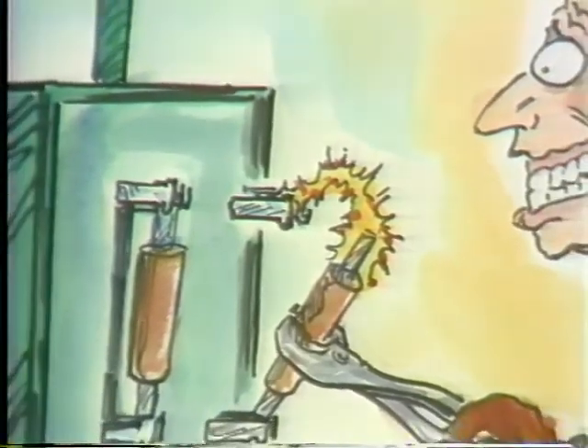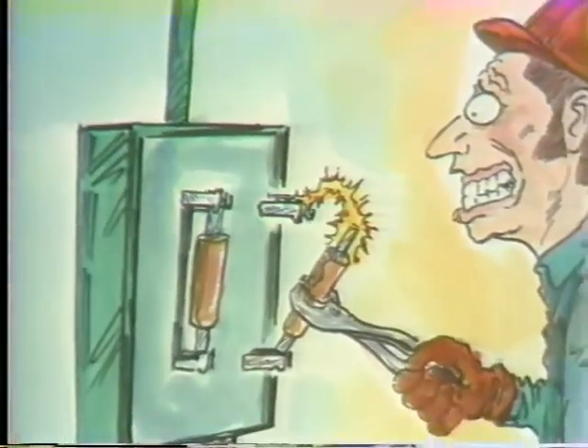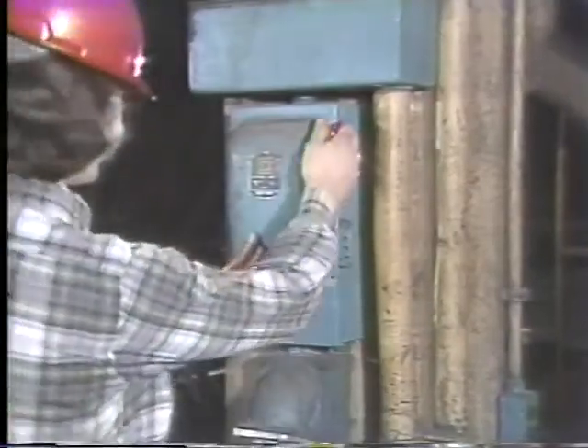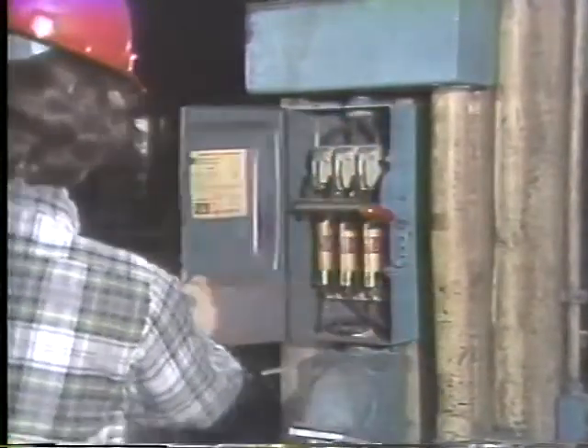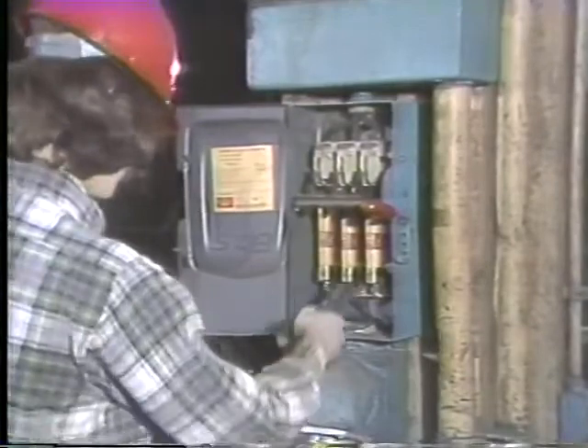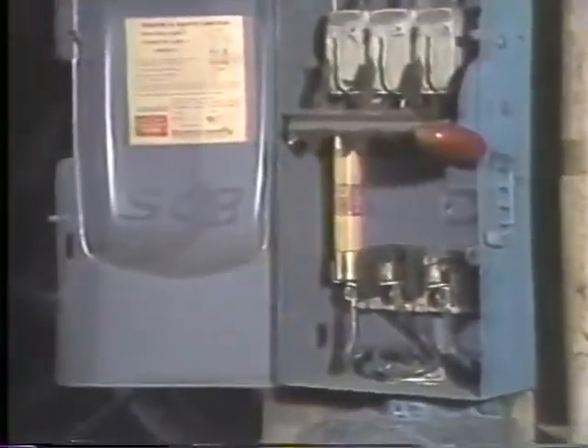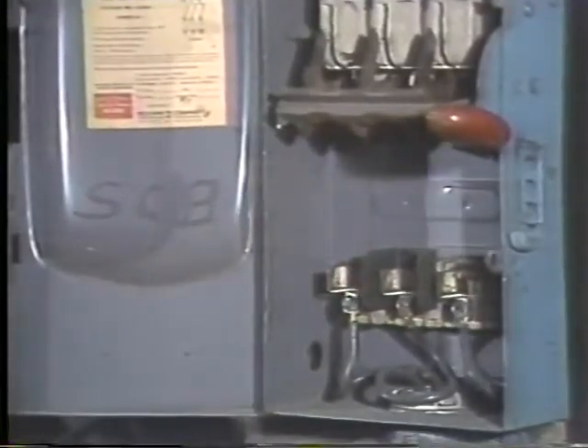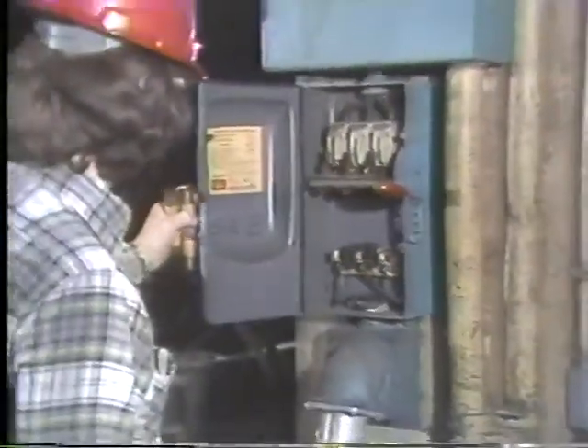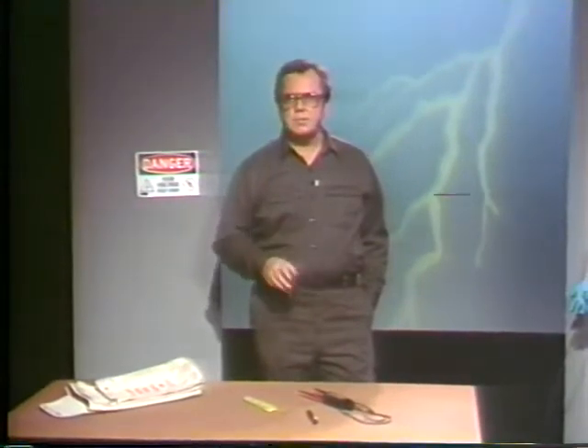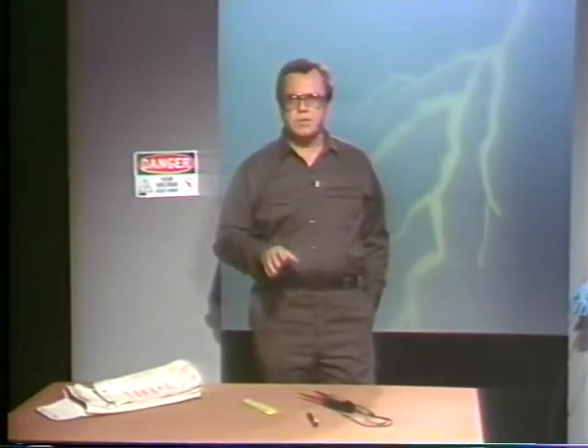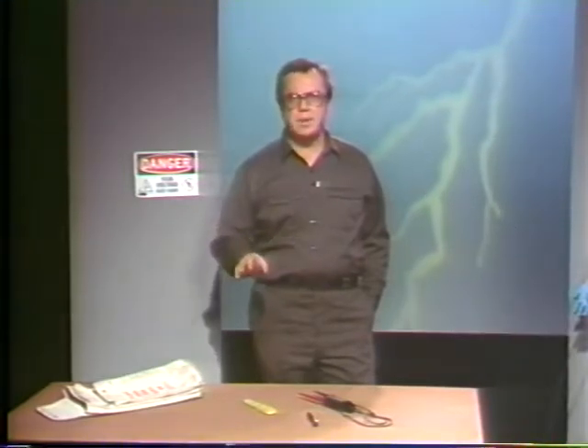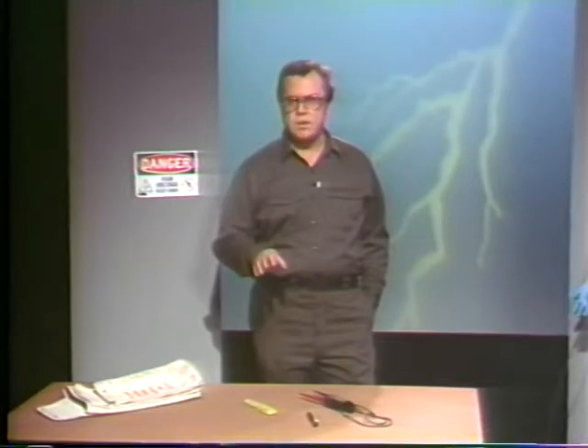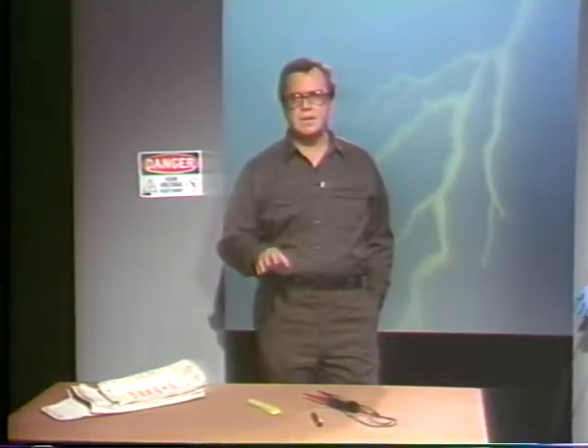For example, pulling out one end of an energized fuse. It's a much better idea to cut the power first, and then, just to make sure, pull each fuse with a sharp tug so both ends come out at once. If it's not possible to de-energize a box before pulling fuses, unload the fuse box. That is, turn off whatever's being powered by that line. If there's no current draw, you're much less likely to get an arc.